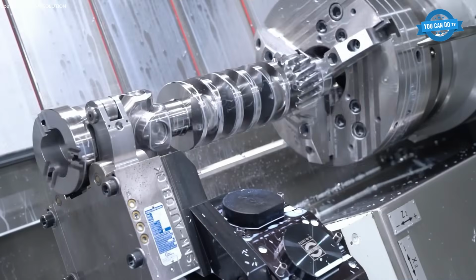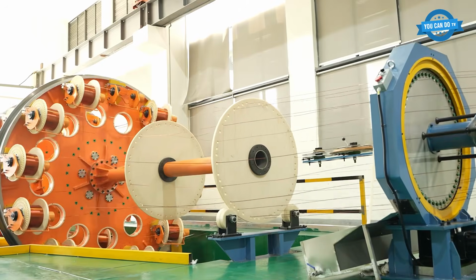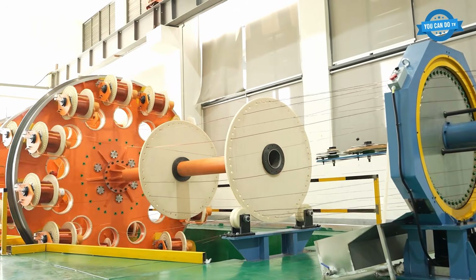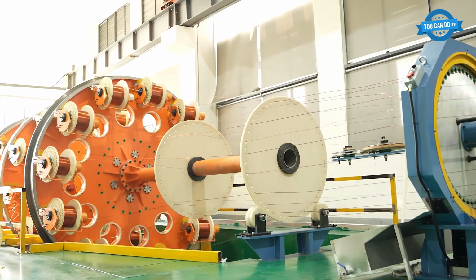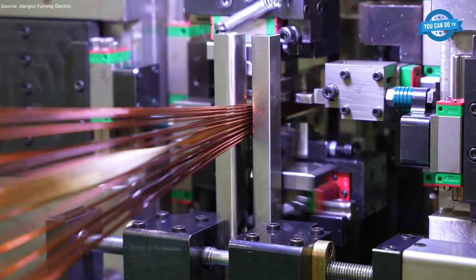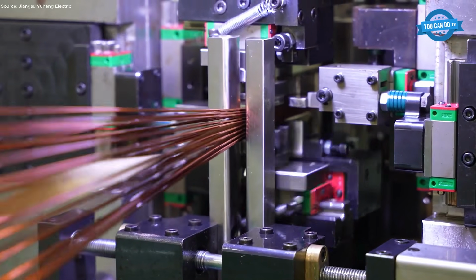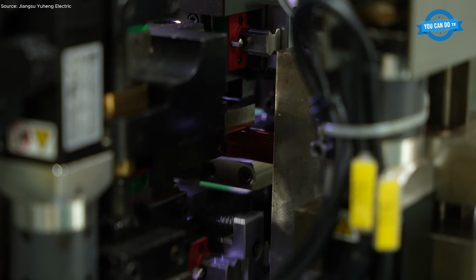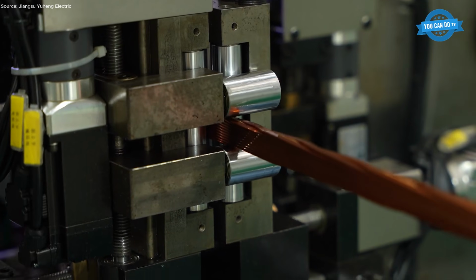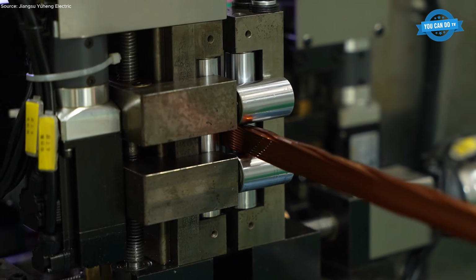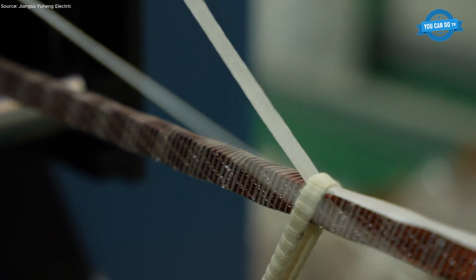Continuously transposed conductors are high-efficiency conductors used in power transformers. Multiple insulated rectangular copper or aluminum wires are continuously transposed along the length, minimizing eddy current losses, balancing current distribution, reducing hot spots, and improving overall electrical and thermal performance.